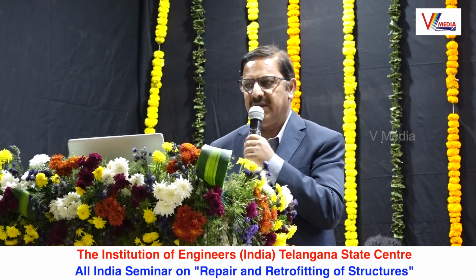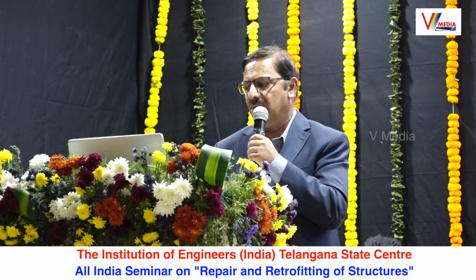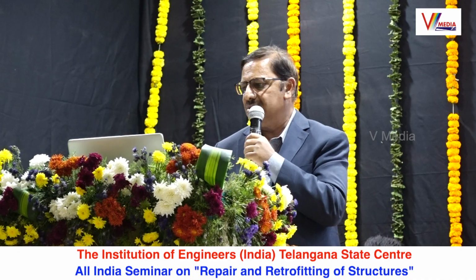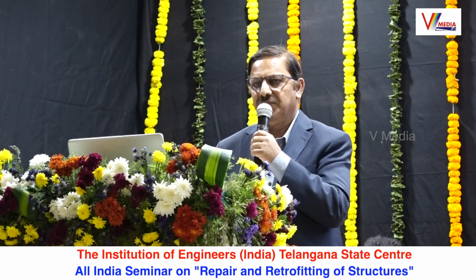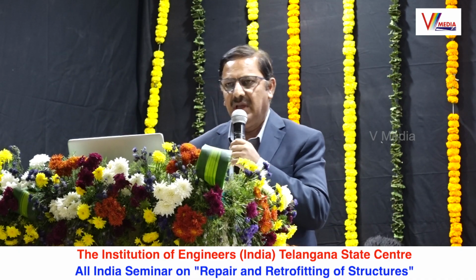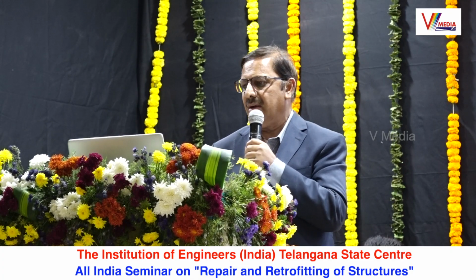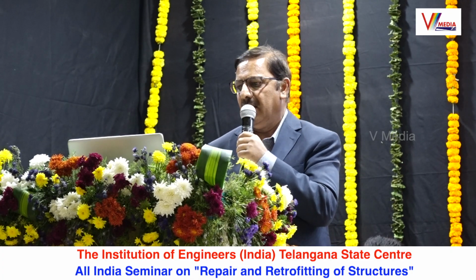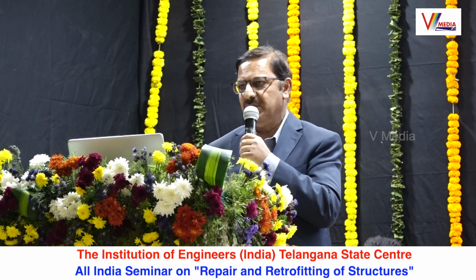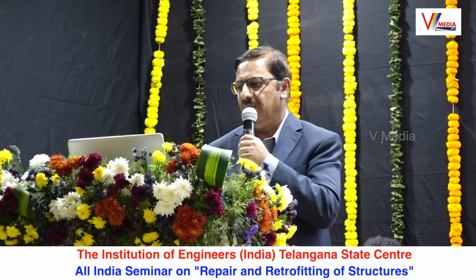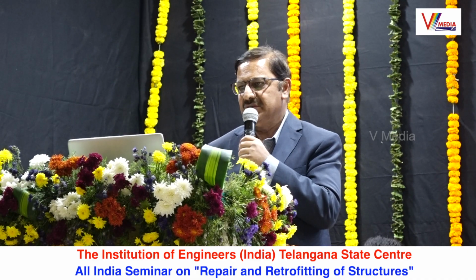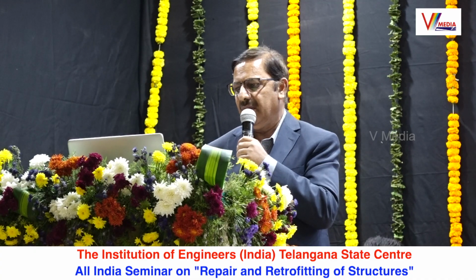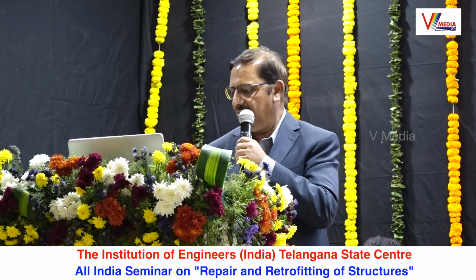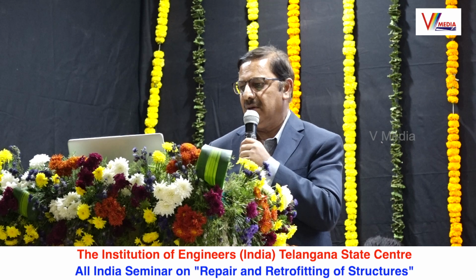So we are applying current, from an external source or through a sacrificial anode, to make the anodes cathodes. The beneficial effects of cathodic protection in concrete are that hydroxyl ions are collected near the steel, which increases the alkalinity, and chloride ions, because they are negative, are driven away from the steel. That's why the steel gets more passivity, and because of that, with time, the current demand reduces.